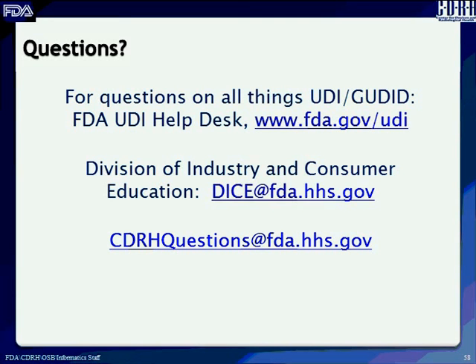I have another question then. FDA PT code and GMDN PT code, either one we have to enter, right? Not both. Correct. We wouldn't want you to enter duplicate codes. So if you were to give us a GMDN code, we wouldn't want you to give an FDA PT code for that same GMDN code. So either or. Okay. Thank you.